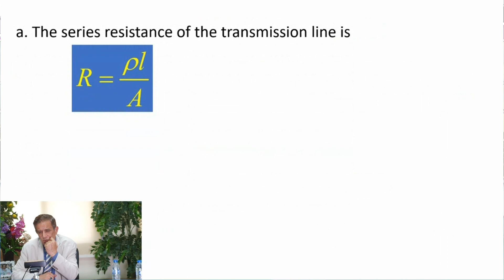Let's first start with the resistance. Resistance, as we saw before, is rho multiplied by L over A. I have the radius of the conductor. This is hard drawn aluminium conductor, so I have to take the rho, the resistivity of aluminium. We explained resistivity before; it's best for silver, then copper, then aluminium. We've selected aluminium because it's cheaper and lighter.